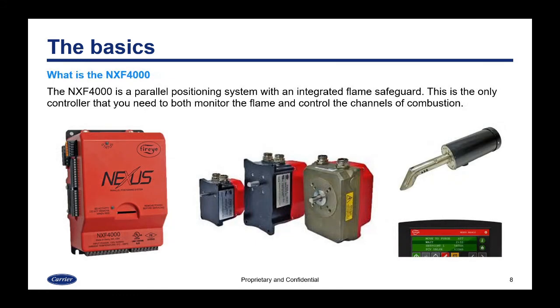So what is the NXF4000? The NXF4000 is a parallel positioning system, as we just described, with an integrated flame safeguard. This is the only controller that you're going to need to both monitor the flame as well as control the channels of combustion.